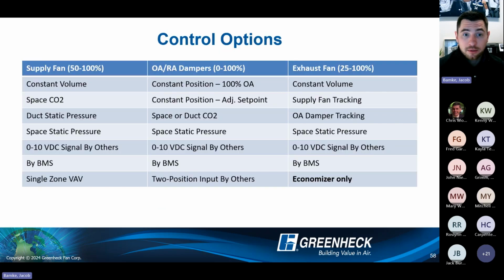And then control options. I won't cover this too in depth here, but you can see obviously supply fan, partial recirc, dampers, and exhaust fan. A lot of different options. If something changes in the field to benefit with our controller, it's very easy to switch from one of these to another without a big program update. You just get into this menu for dampers, change it from space pressure to constant position, and that's how it's going to be operating. So very easy to make on-the-fly adjustments as well.